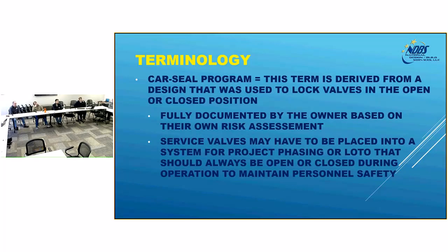Car seal program. So you guys have heard of LOTO procedures. So in some cases, an owner may want to keep a valve locked open or in a locked closed position during operation to mitigate risk. So I'm talking about these risk assessments. So in the pharmaceutical world and the industrial manufacturing world, on a system-by-system basis that's carrying category M fluids or any fluid really that touches the process, an owner has to sit down and develop a documented risk assessment of what can happen.